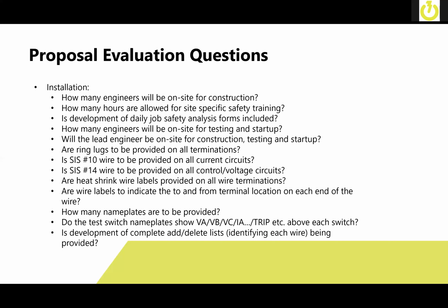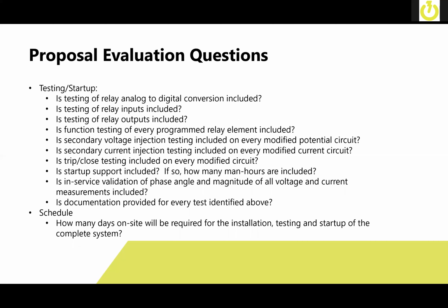Are nameplates being provided, and do those test switch nameplates show the specific functions such as voltages, current, A, B, and C, trip, etc. above each test switch? And is development of a complete add-delete list being provided? From a testing and startup standpoint, is testing of relay analog to digital conversion included? That would be an A to D converter, injection of currents and voltages into the relay. Testing of relay inputs and relay outputs, function testing of all programmed relay elements.